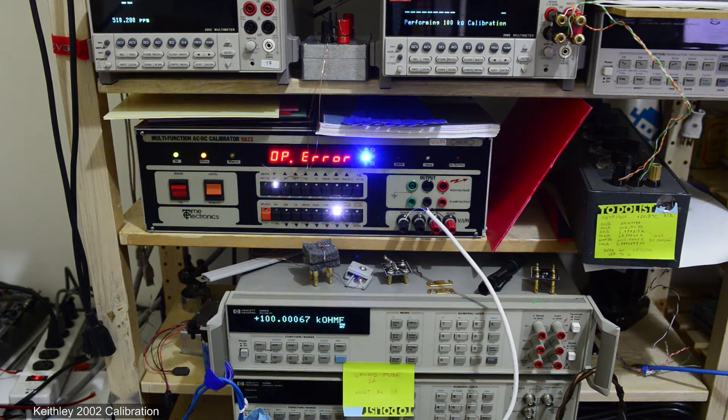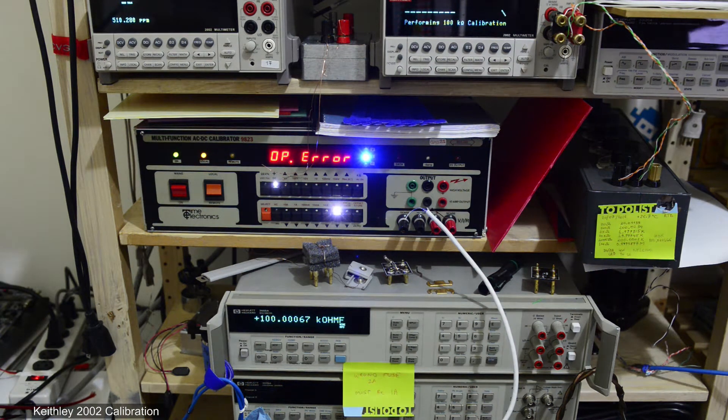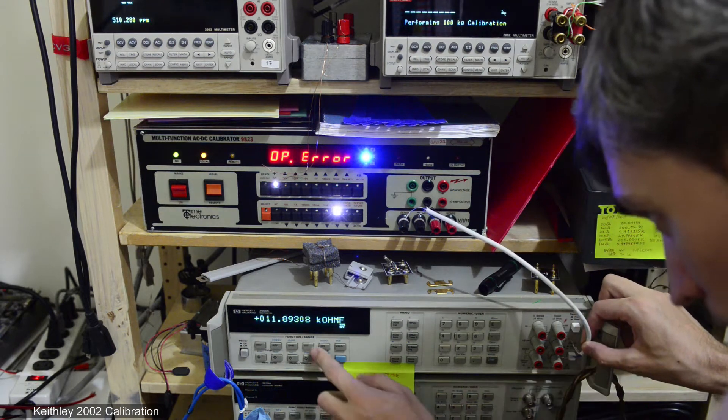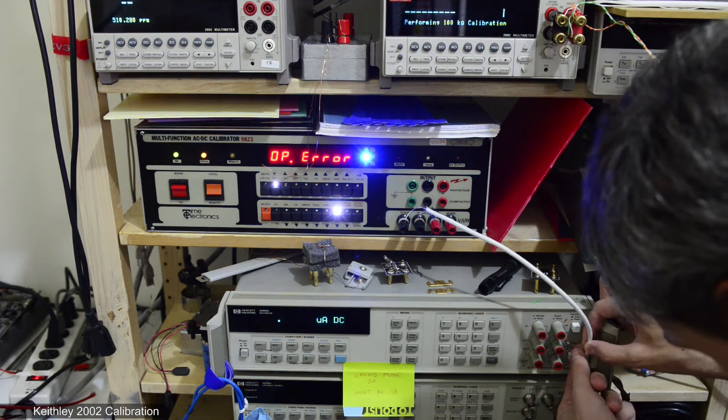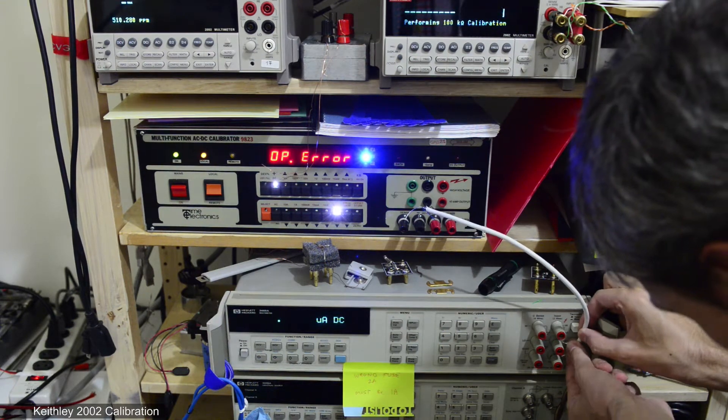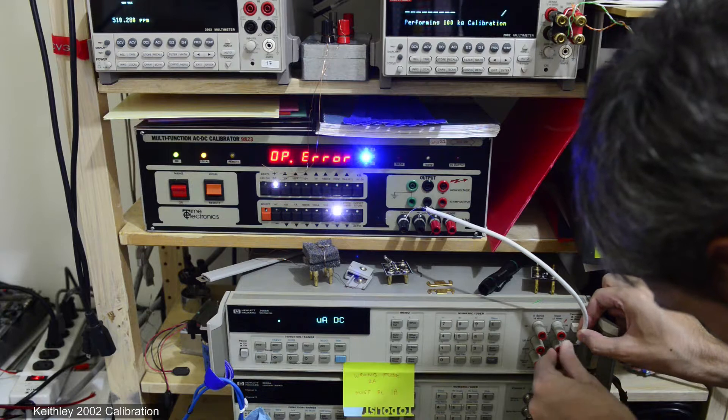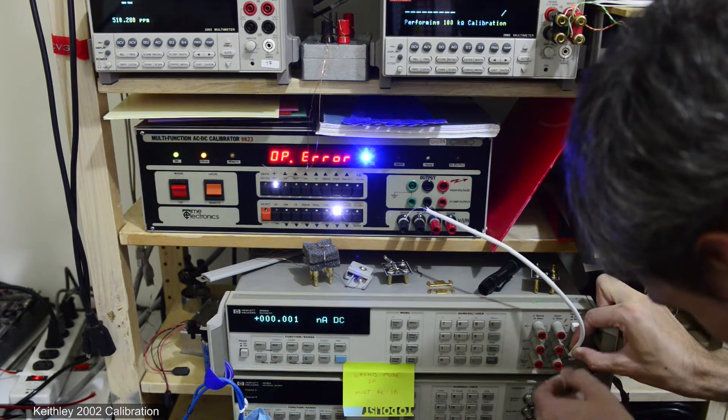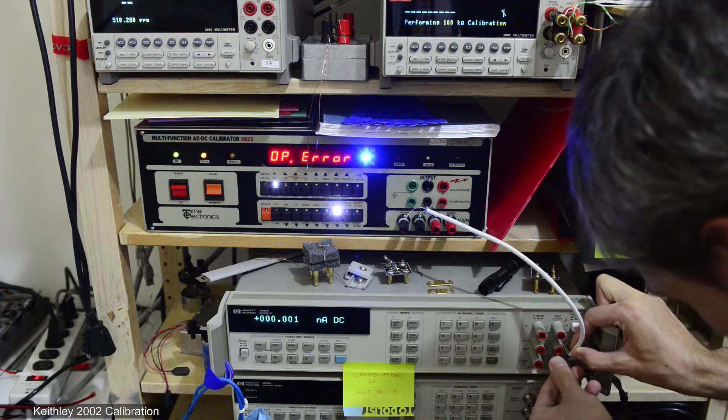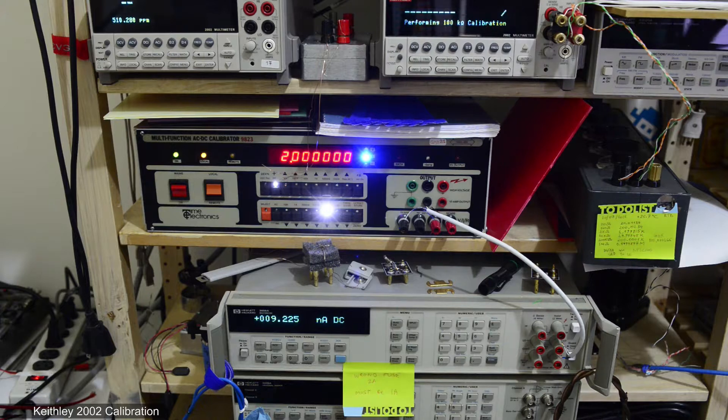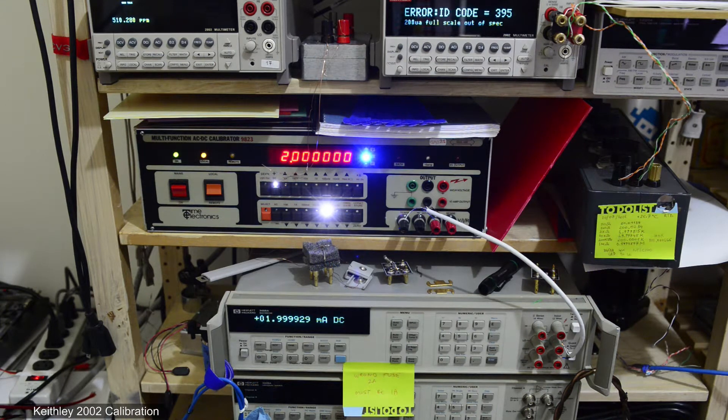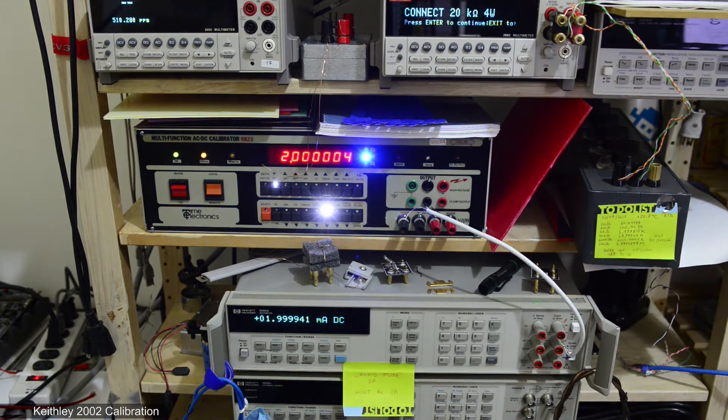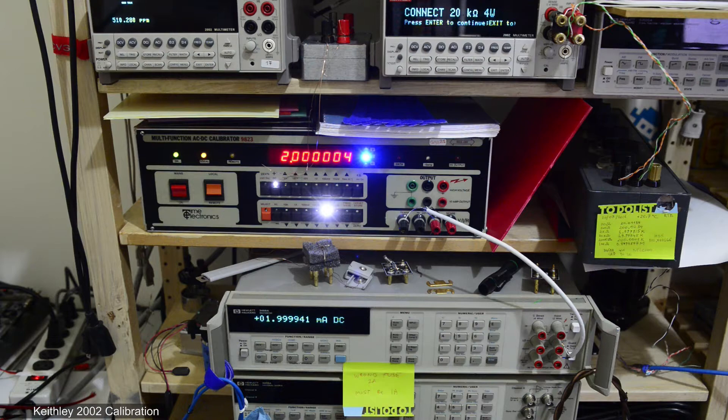I already tested all the resistance values required for calibration and now I tested 100 kilo ohm. You can see the calibrator is showing output error since it requires connection to current input terminals on the DMM to source any current. That is normal and can be reset after the connection is done. Here you can see two milliamps sourced into the HP DMM.